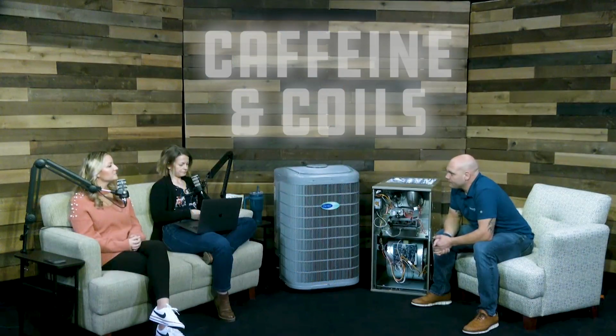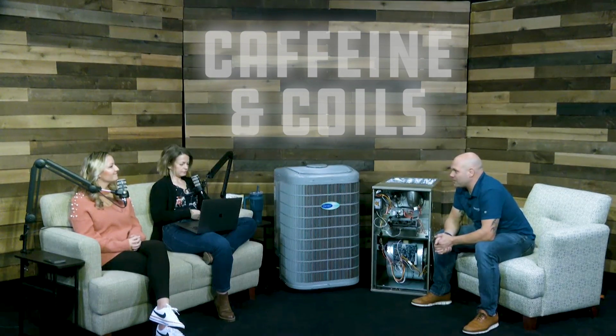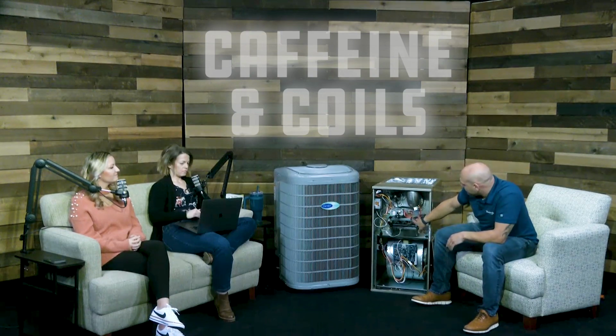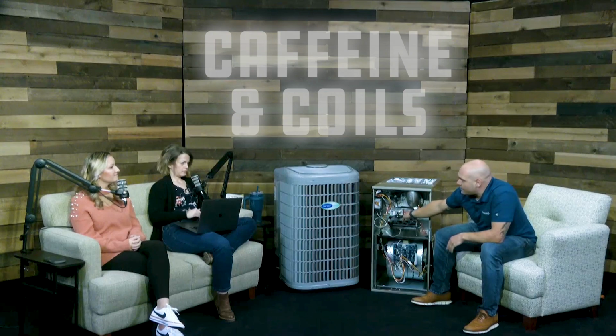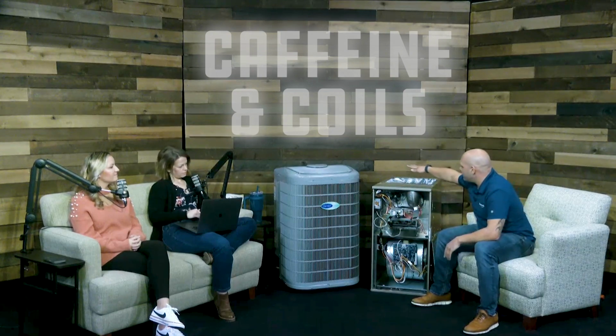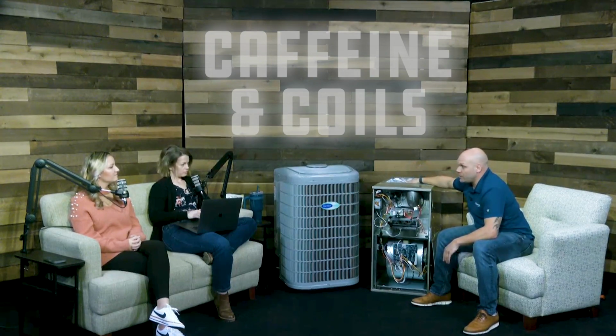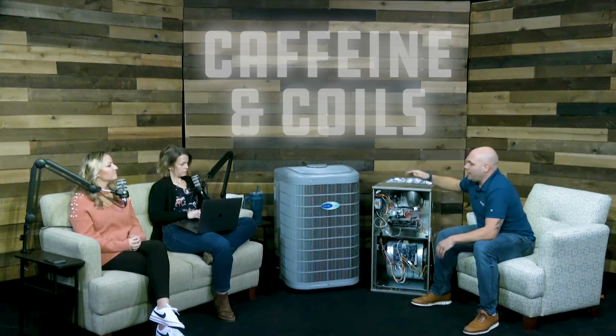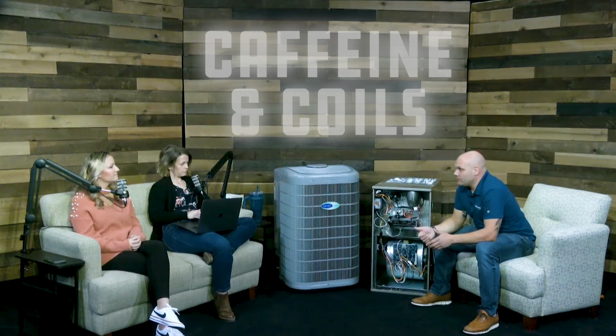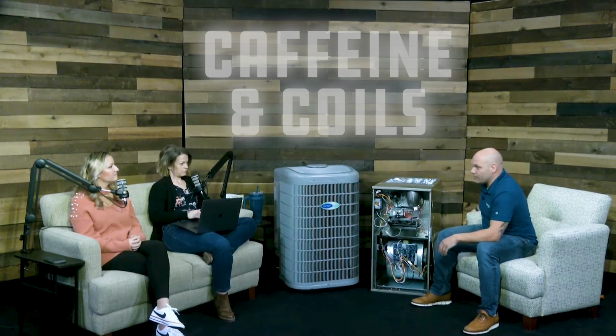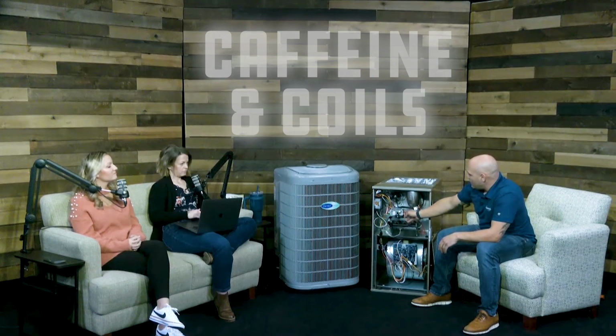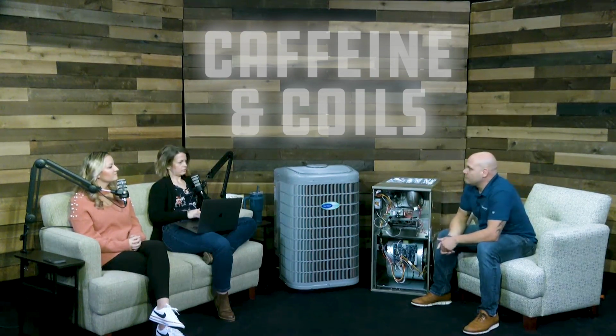Okay. Yep. Nice. So, with code 33, we've kind of just scratched the surface. Another common code 33 issue could also be your high temperature switch. So there's a switch that goes inside your heat exchanger portion, and if the heat exchangers get too hot, that switch can activate as well. And a lot of times that is due to airflow. So lack of airflow, a dirty filter, could actually cause the high temperature switch to activate.